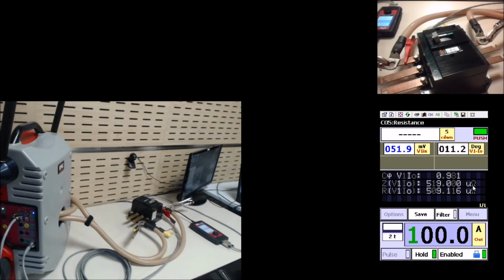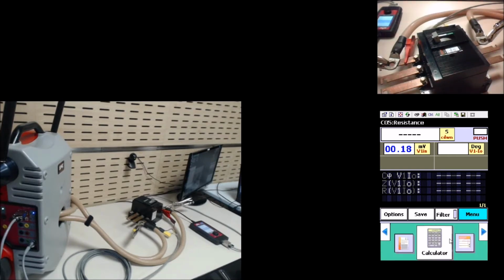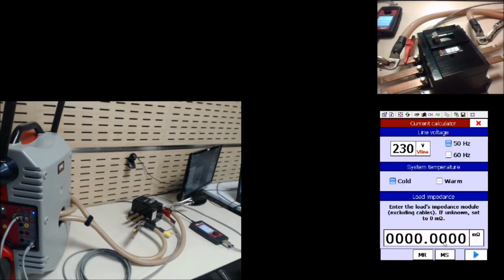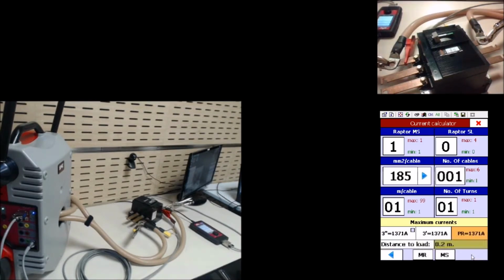All right. So if we take this impedance value and go to the current calculator, also included in the Raptor interface, we go to the menu, select the calculator, and enter this impedance here. Okay, this is 519. We enter the type of cable that we have, which is a 120 square millimeter section. We just have one cable. This is 3 meters long, and we are doing 2 turns.